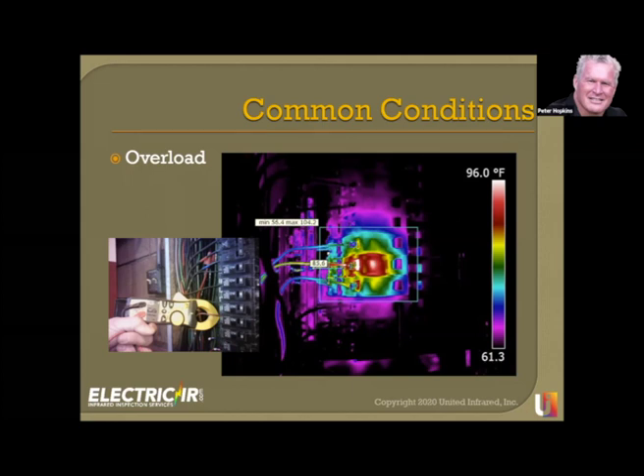So I see the problem thermography-wise. Now I take a load reading and I've identified that we've got an overload. This goes into my report: the system's got 19.1 amps on a 20-amp circuit. You need to reduce the load and recheck the connection. So it's an easy one.